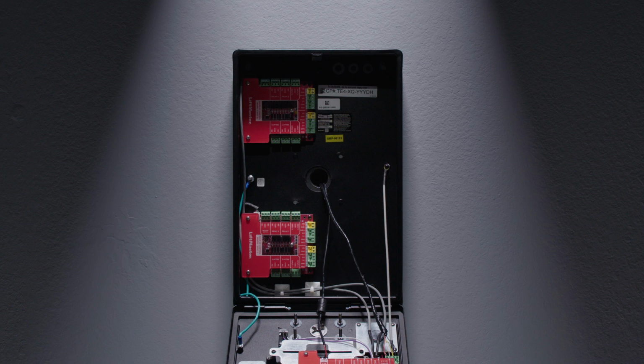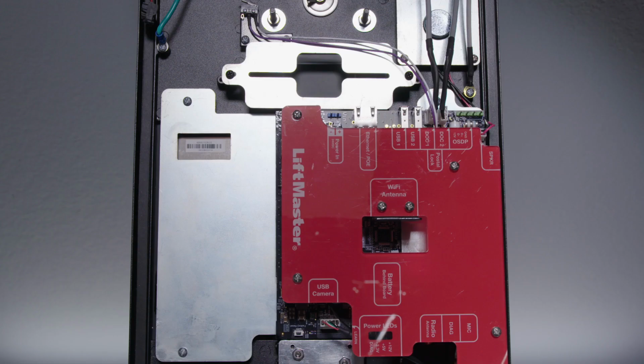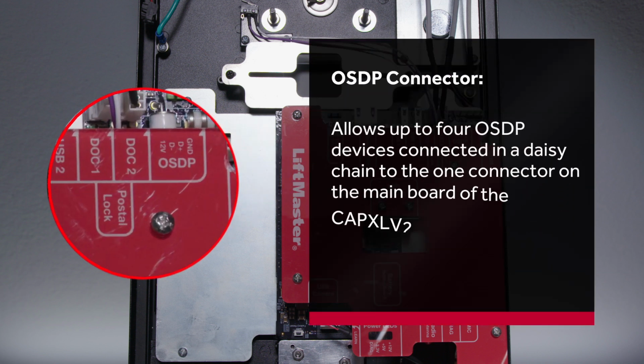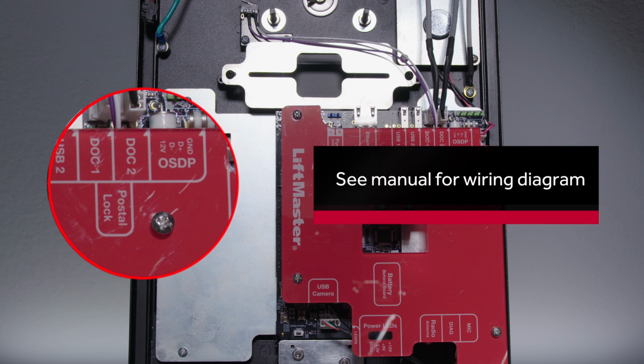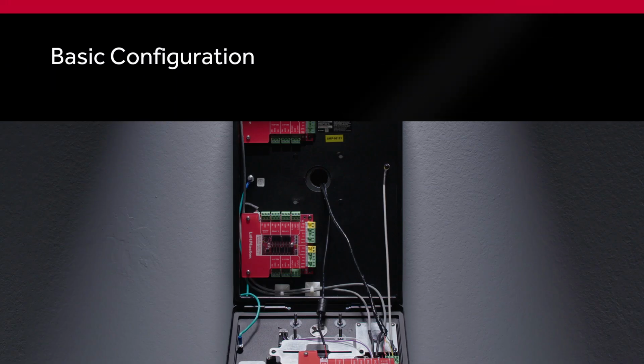When advanced configuration mode is activated, the four auxiliary relays become available. This makes it possible for each of the four Wiegand devices to be mapped to any one of the eight available relays. In addition, the CAPXLV2 features an OSDP connector. This connector allows up to four OSDP devices to be connected in a daisy chain to the one connector on the main board of the CAPXLV2. With the addition of the OSDP port, you are now able to map eight different input devices to any of eight relay-driven devices. Let's discuss use cases for basic and advanced configurations.